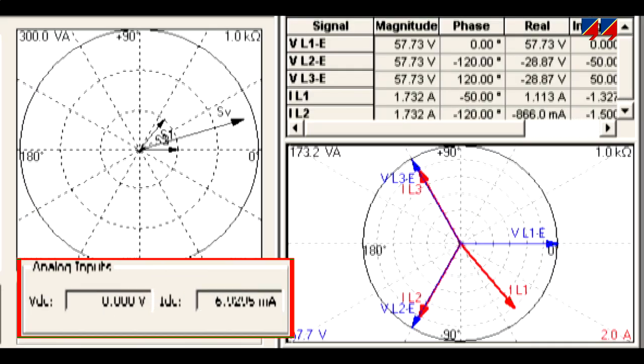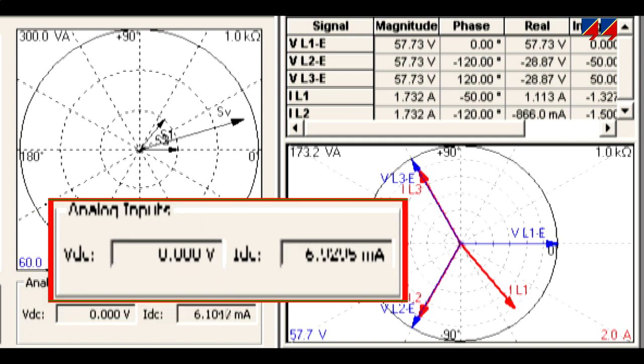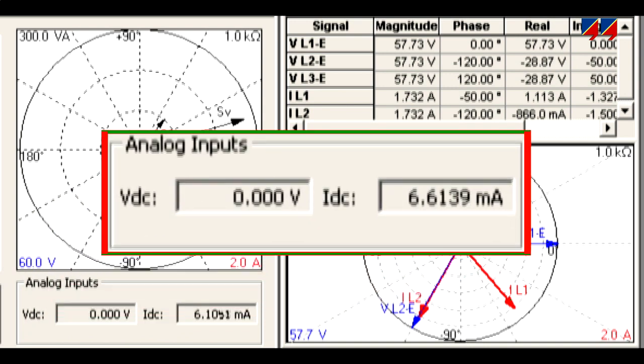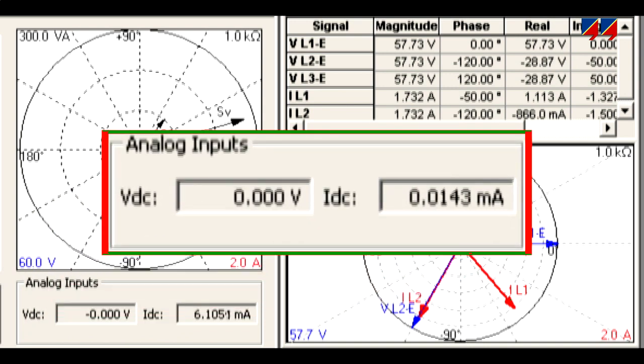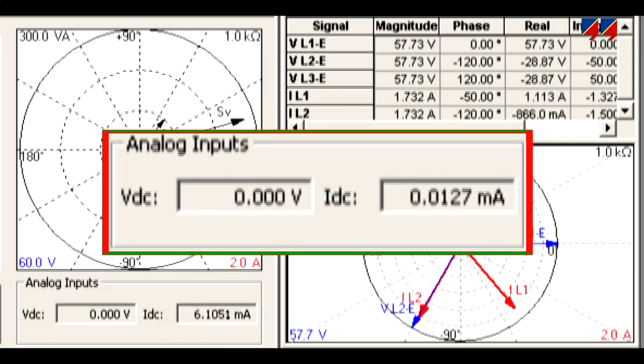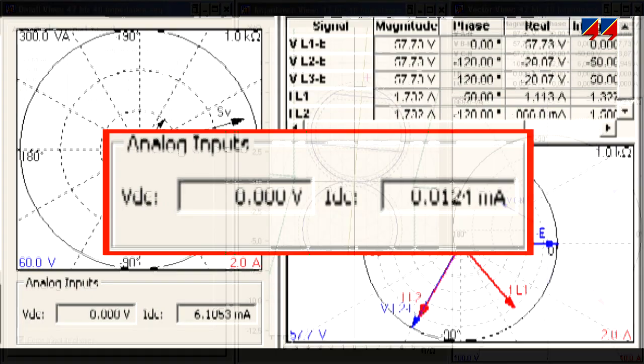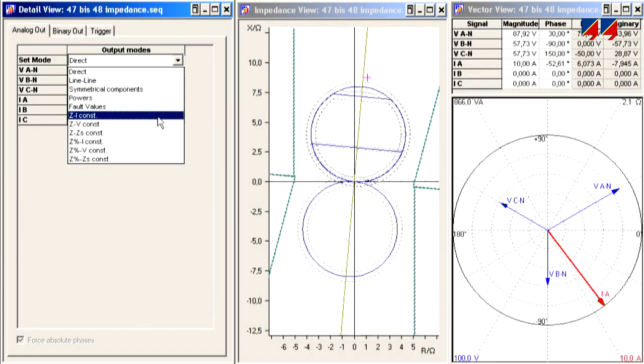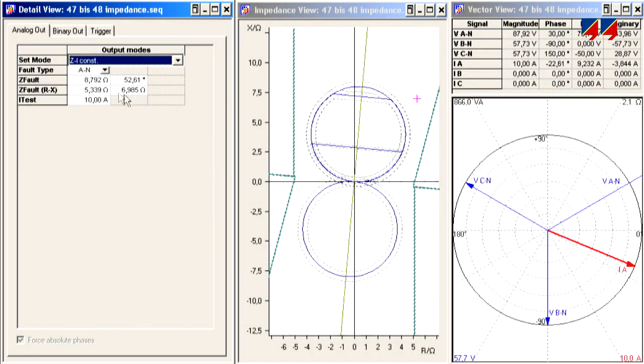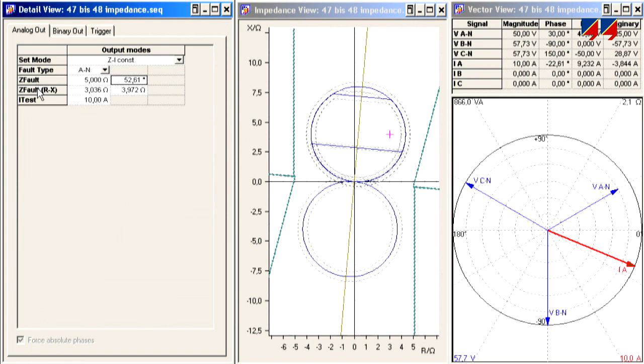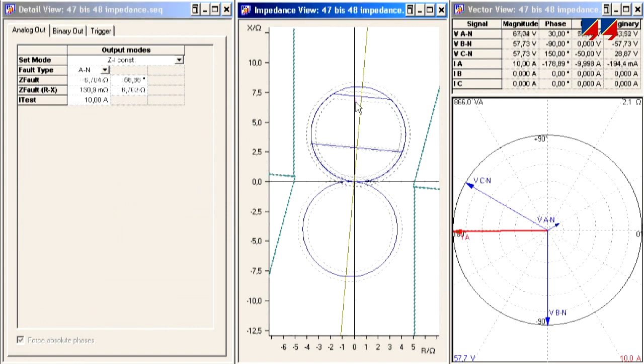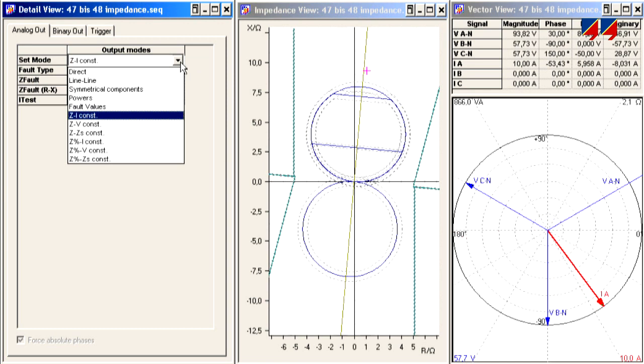For manual testing, the values of DC current and voltage outputs from measurement transducers are displayed. Output quantities can also be defined as impedances, either as absolute values or as a value relative to a distance relay zone setting.